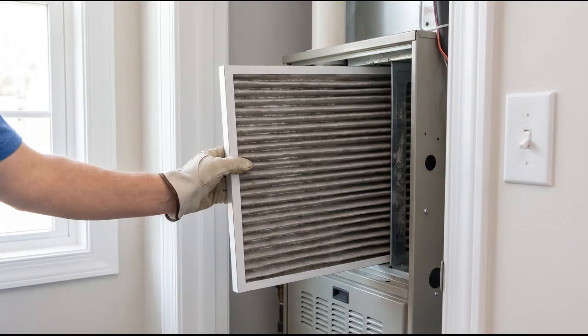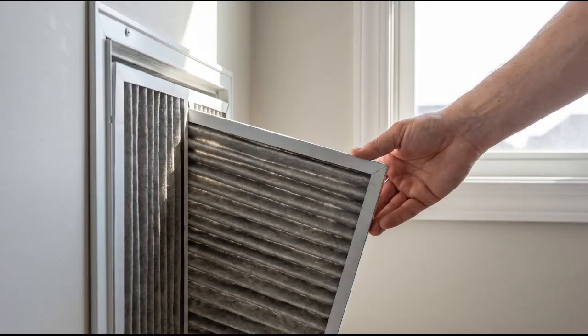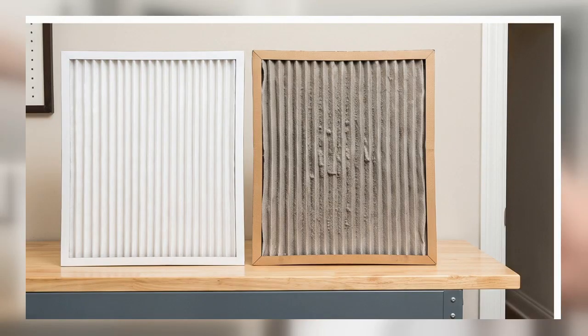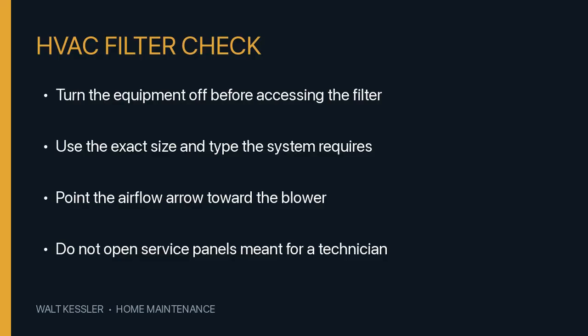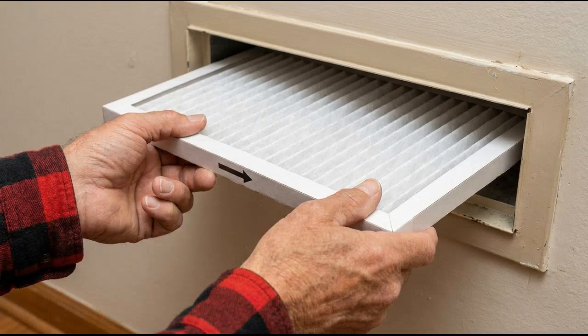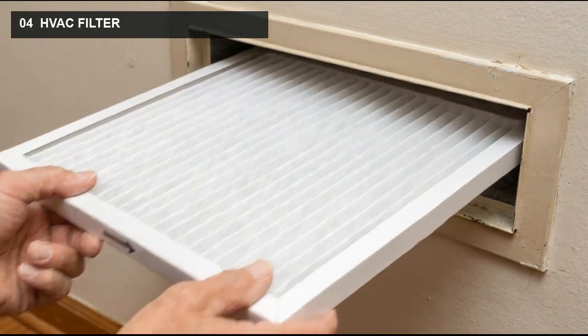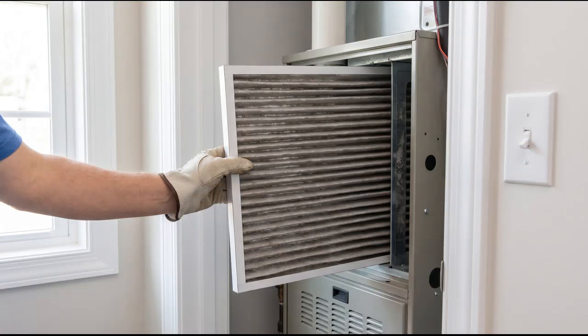Energy Star warns that a dirty filter can increase energy use and damage equipment, but do not solve that by installing the highest rated filter you can buy. The system must be designed for the filter you use. If access requires opening an equipment panel, you cannot identify the filter specification, airflow stays weak, or you see moisture or suspect mold near the intake, stop and call the HVAC contractor.